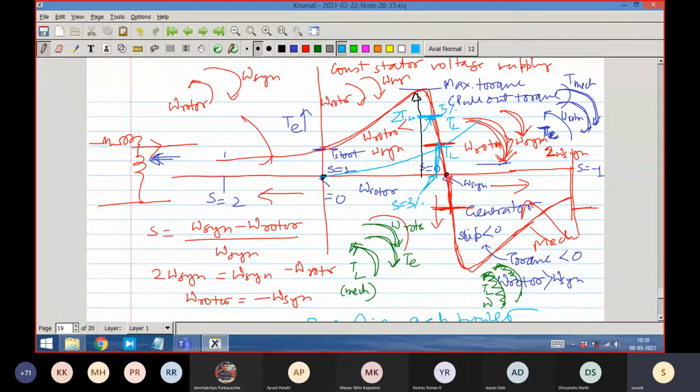Right? So this way we have to keep that in the design. That means the original value of the resistance we have to reduce. That means we have to use a thicker conductor so that the slip actually comes back to about 3%. That can be possible by changing the machine, going to the higher machine. So the clear understanding of this has to be there. Even though from the same machine we can achieve higher torque, that is not our rated operating point.